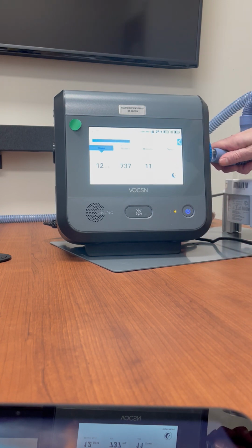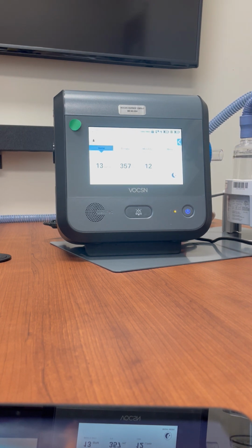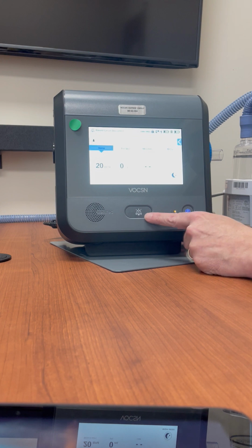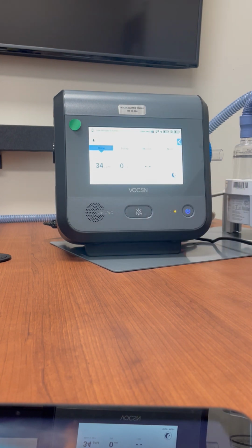We're going to take the entire circuit off. But again, if your leak is too high, you can get this alarm also. First, it'll be a low inspiratory pressure alarm, which switches over to a patient disconnect alarm. This button's alarm silence. It's a bell with an X through it. It'll quiet that beeping down while you troubleshoot to see what is causing that leak.